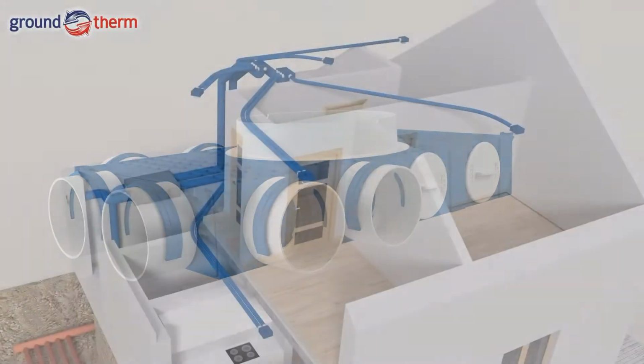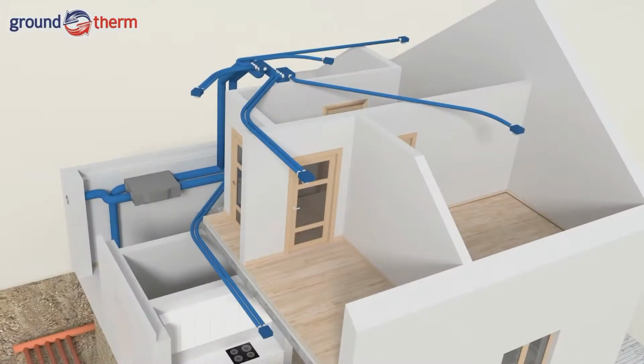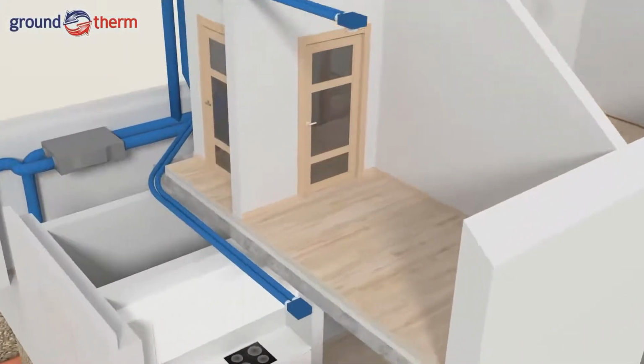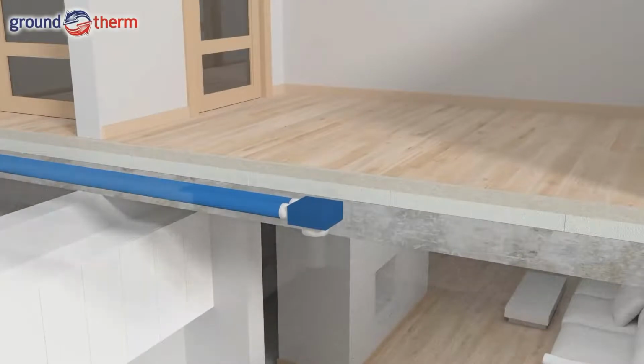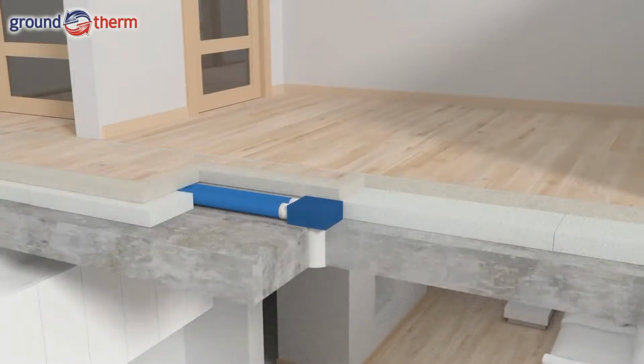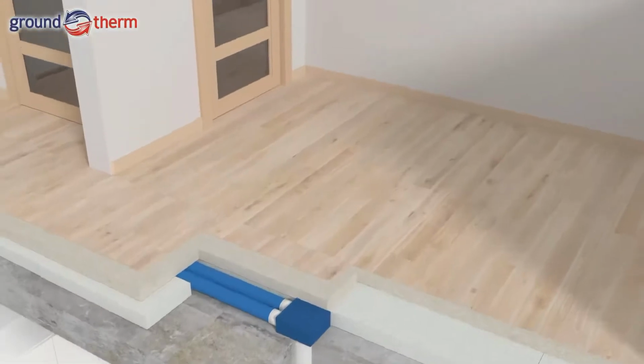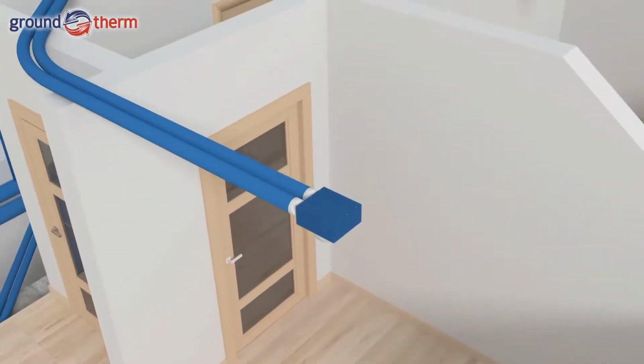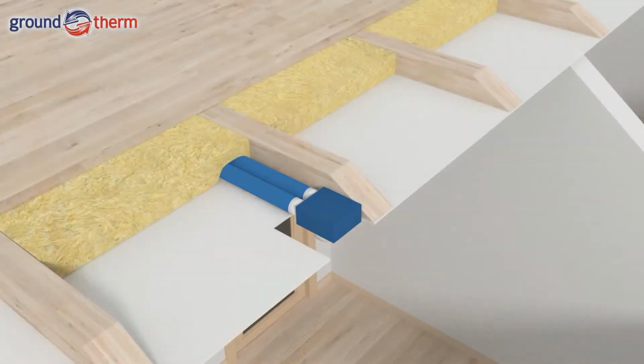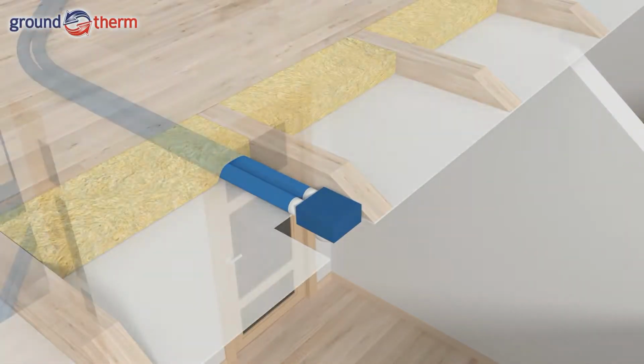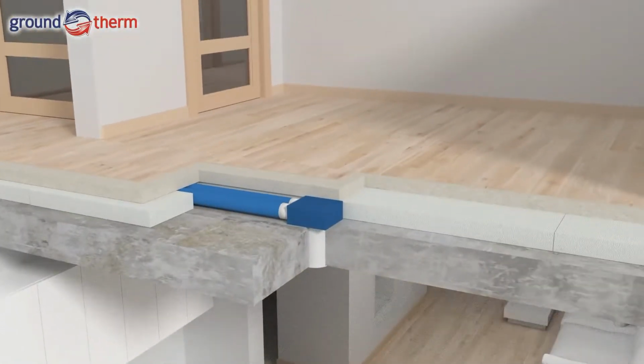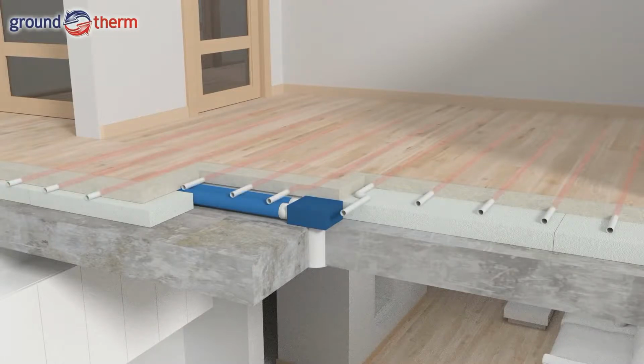The VENTIFLEX ducts, manifolds and plenum boxes that supply air on the ground floor can be located in the extruded polystyrene insulation layer below the floor screed, while the ones that supply air on the first floor are usually installed above the false ceiling, below the insulation layer. Small sizes of the ducts, plenum boxes and manifolds do not hinder in installing the floor heating system and make it possible to perform the aesthetic ventilation system that is practically invisible to the eye.